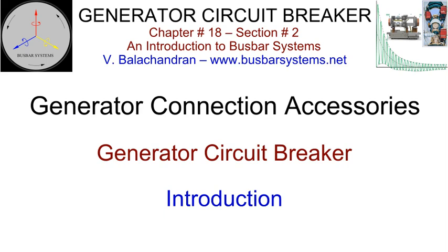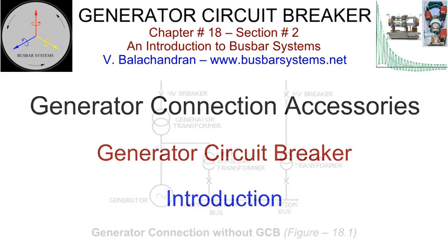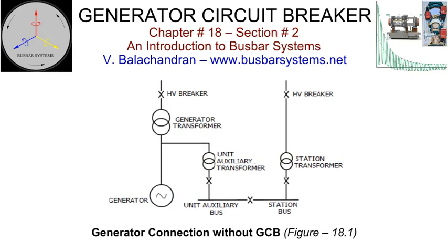The absence of higher rated capacity of these breakers resulted in generators being directly connected to the generator transformer, with tap-off to auxiliary loads, excitation system, and surge protection voltage transformer cubicles. The synchronizing with the grid was carried out at the high voltage end of the generator transformer. All power stations with large-sized generators require power to run their respective auxiliaries. The unit auxiliary loads could be quite significant in the case of thermal, nuclear or gas power plants and marginal in the case of hydroelectric power plants.